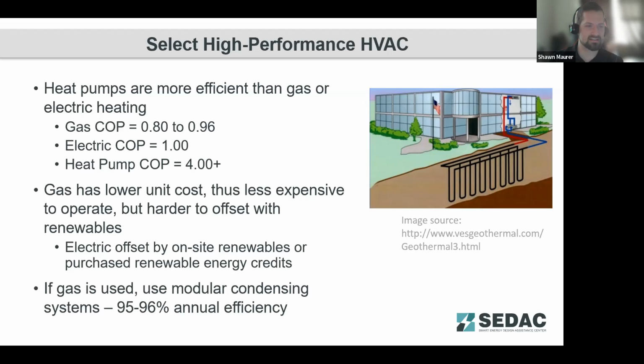There is a consideration that gas does have a lower unit cost, and so it's typically less expensive to operate, but it's a lot harder to offset that with renewables if you're targeting net zero. It's harder to find renewable sources of combustive gases. You would have to tie into renewable natural gas that's produced from wastewater facilities or something like that that's doing digestion. It's a lot easier for buildings to connect to on-site or off-site renewable solar and wind credits to reach that net zero goal. If gas is used, again, stressing high efficiency combustion systems, modular systems that can maintain operation at their peak efficiency for longer throughout the year is very important.